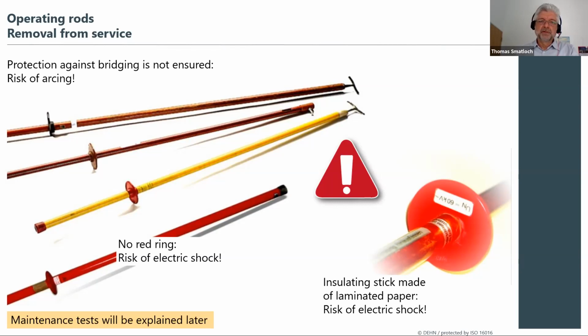One example is this brown tool, as you can see here. It is made of so-called laminated paper. And it turned out over time that this laminated paper is very hygroscopic. That means it attracts water, humidity, and then the insulation is not given anymore. So I have seen real tests with this in our high voltage laboratory that we run here on our premises. And you can really see that there are flashovers over the surface of this material. So this can be very dangerous.